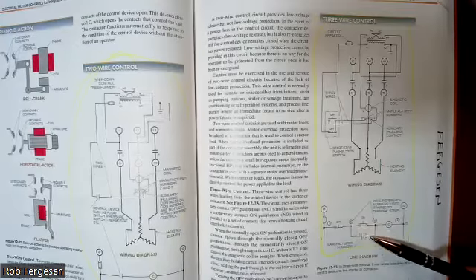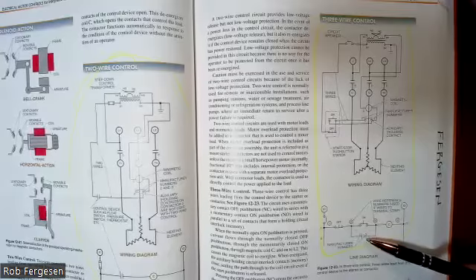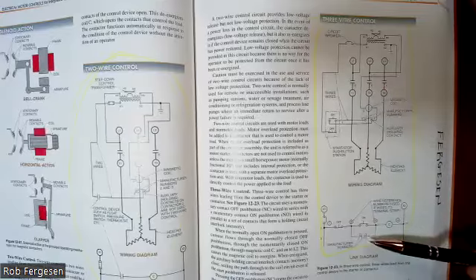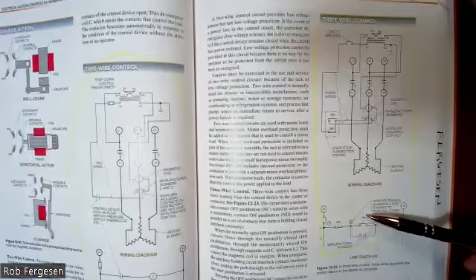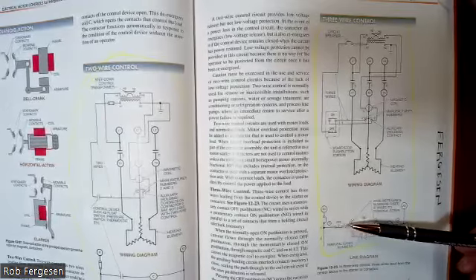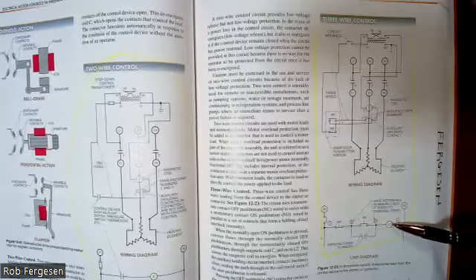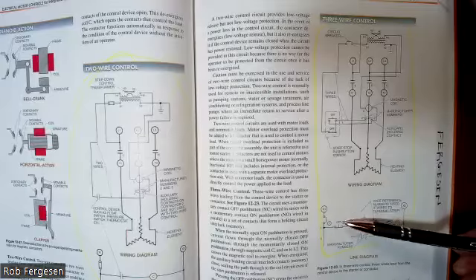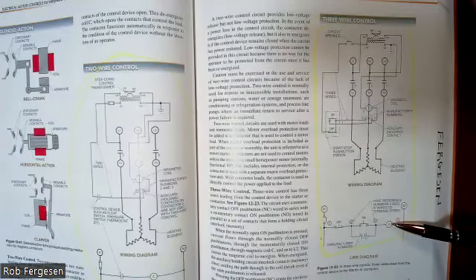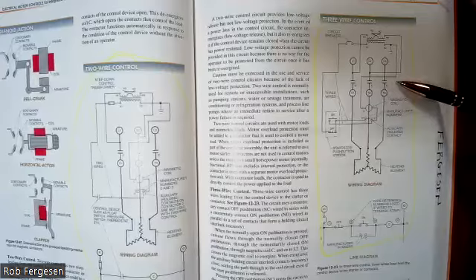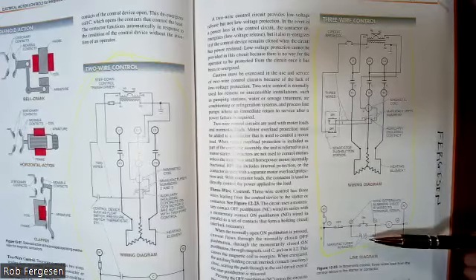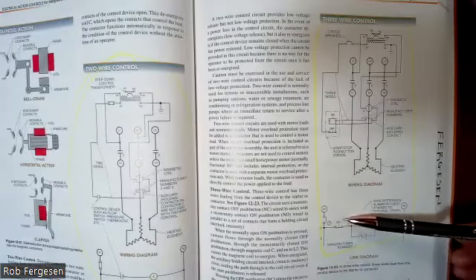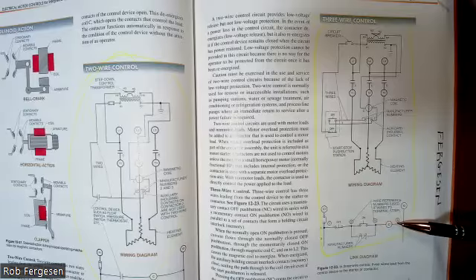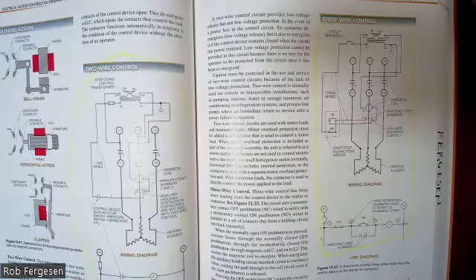And the other diverts around the on push button to a set of contacts that is built into the contactor. That auxiliary contacts, those extra contacts, when I press that on button, my control power flows through the on button. It's already flowing through the off button because it's normally closed, and into the coil. Then that coil engages the contactors. All these contacts close, and the auxiliary contact closes. So now I got control power that goes around through the auxiliary contact, through the coil, and the coil stays on even after I let go of the on button.